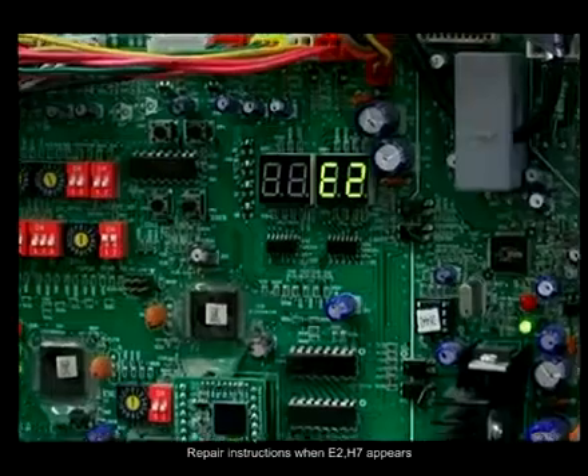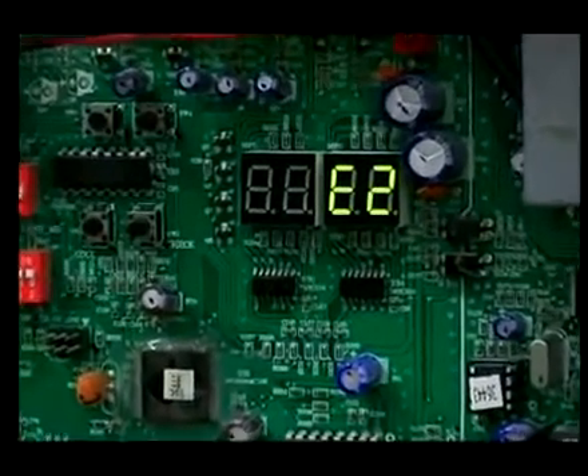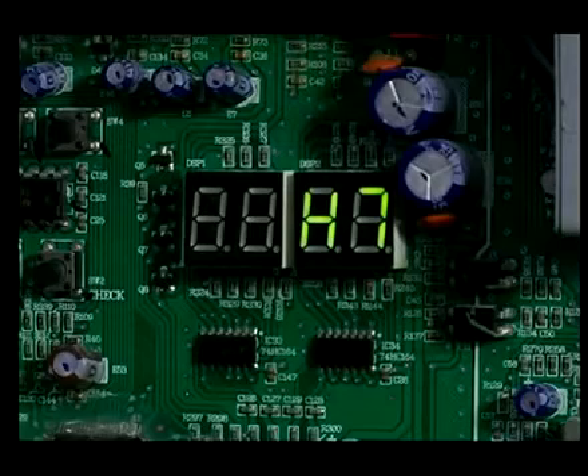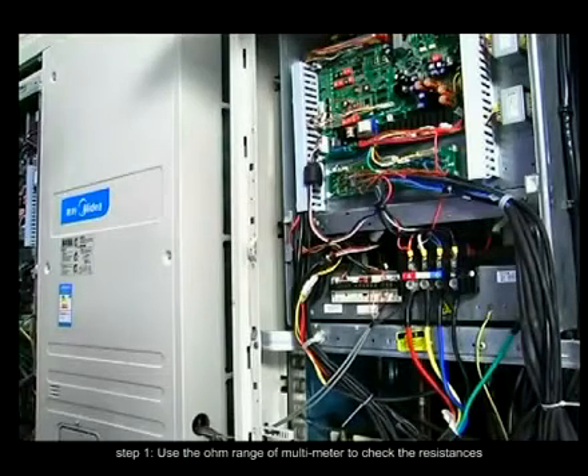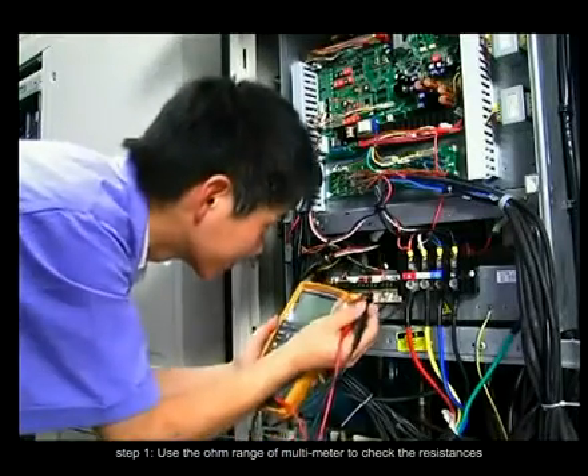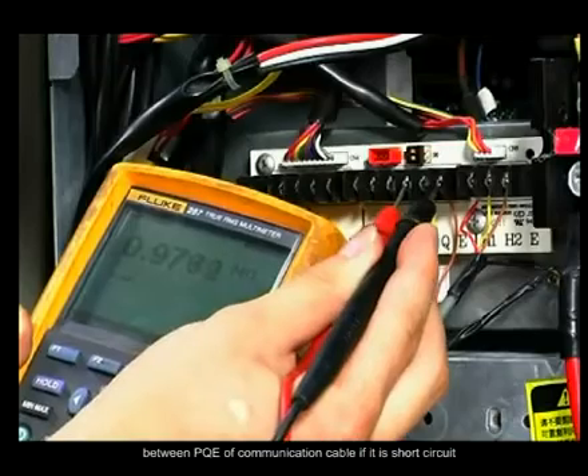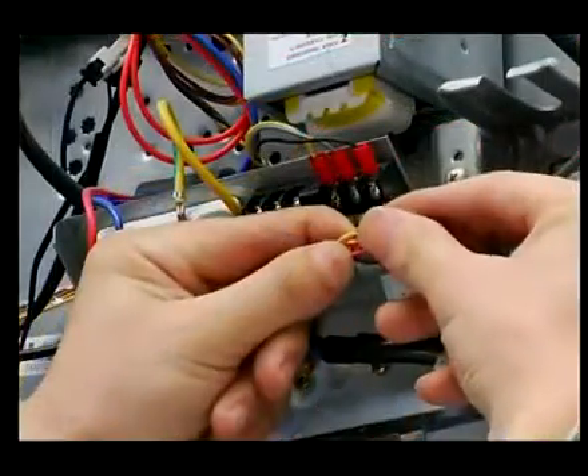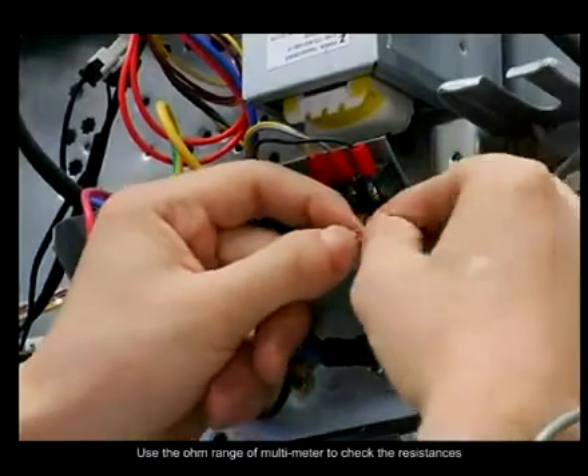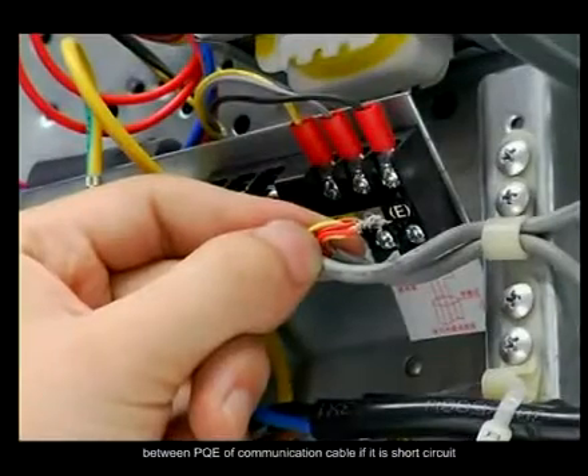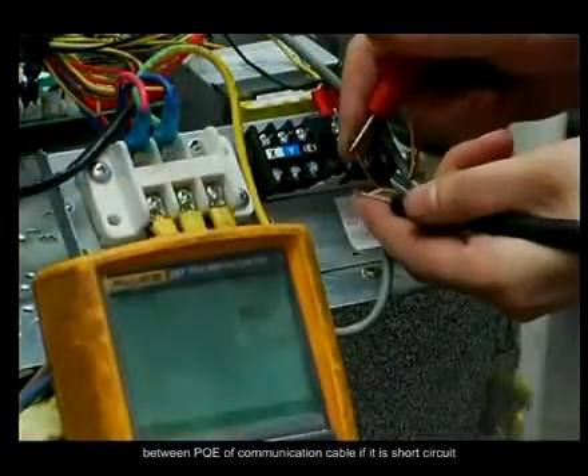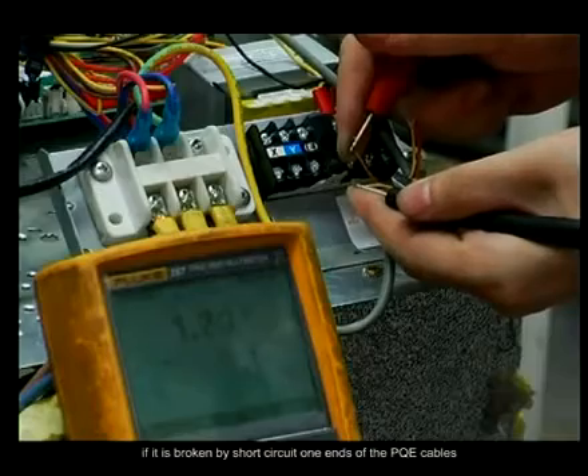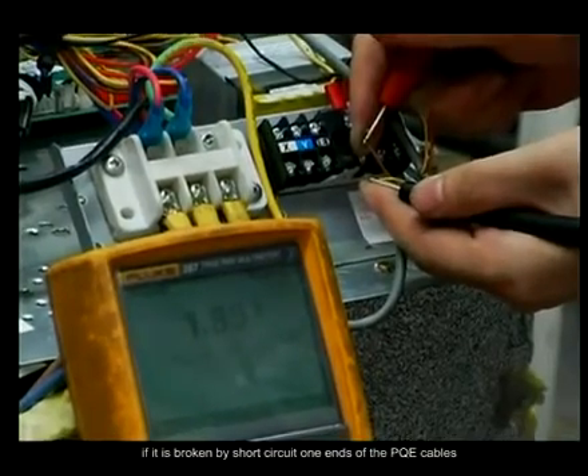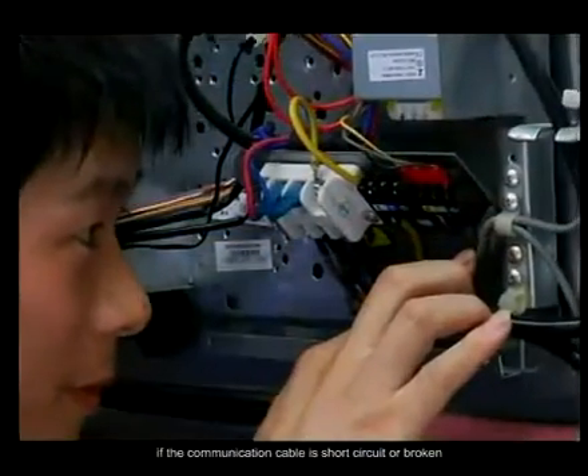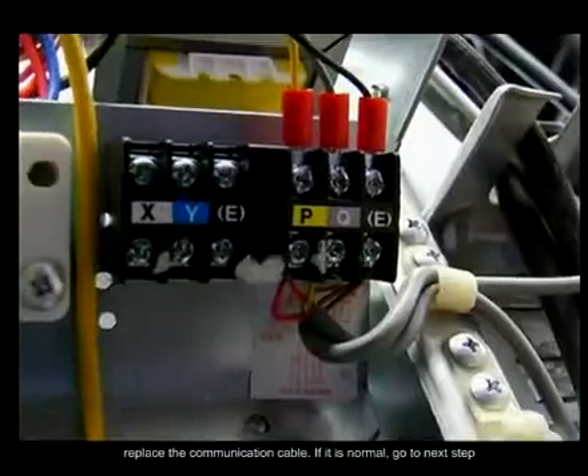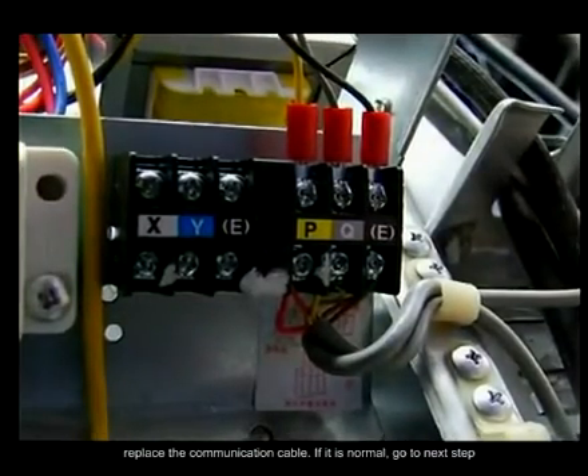Repair instructions when E2 H7 appears. Step 1. Use the OHM range of multimeter to check the resistance between PQE of communication cable if it is in short circuit. Check the communication cable if it is broken by short circuit at both ends of the PQE cable. If the communication cable is short circuit or broken, replace the communication cable. If it is normal, go to the next step.